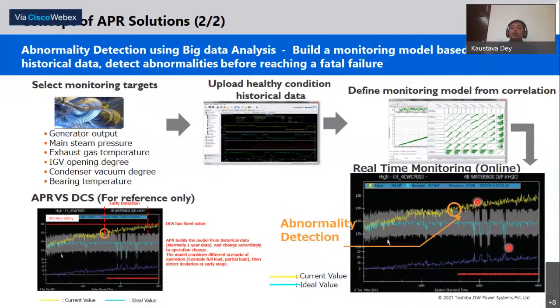But DCS may not know at this time that this parameter has deviated, because this model has been created based on correlation with different parameters of that particular equipment or asset. As a comparison, the DCS value is a kind of fixed value. Suppose for a bearing temperature, the DCS value is fixed, say 90 degrees centigrade, and you get the alert at DCS at that point. But this model can give you an alert in different situations, different atmospheric conditions, different load conditions. This correlation based model will tell you that this particular parameter has gone beyond its operating zone. So this is the beauty of APR apart from DCS.